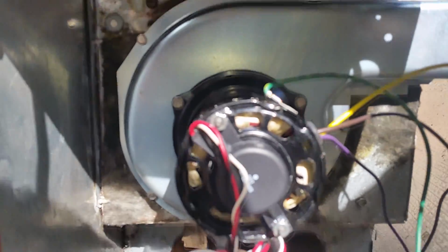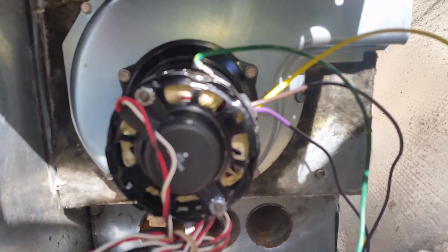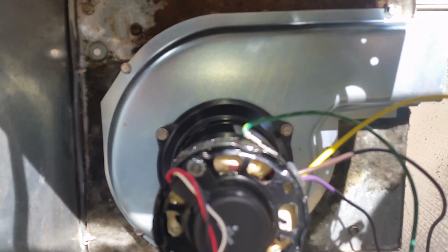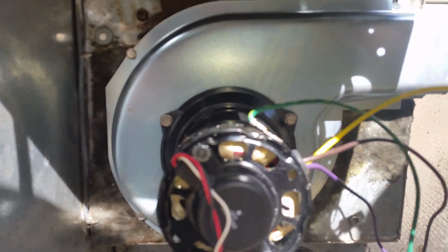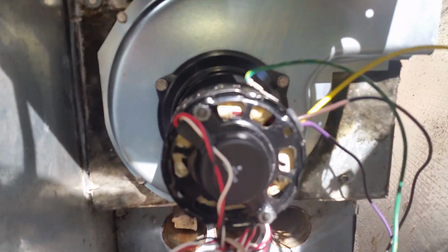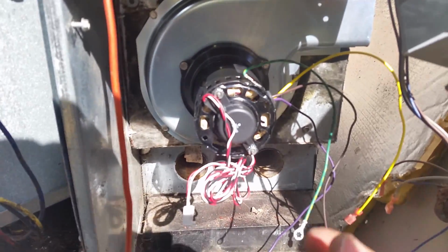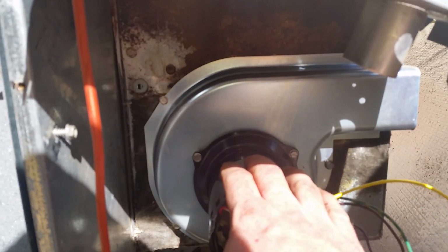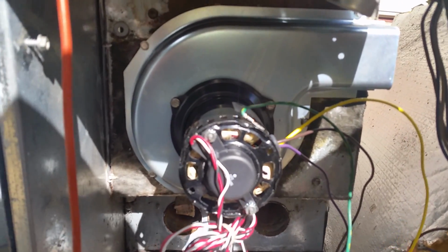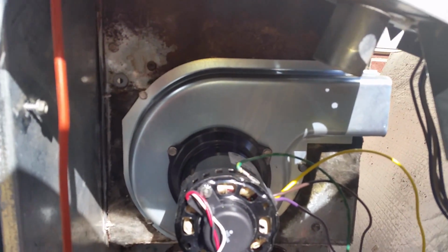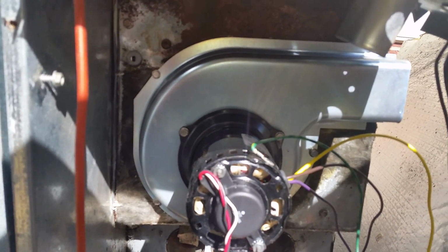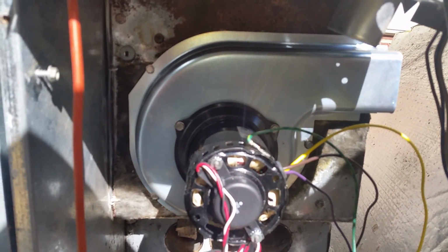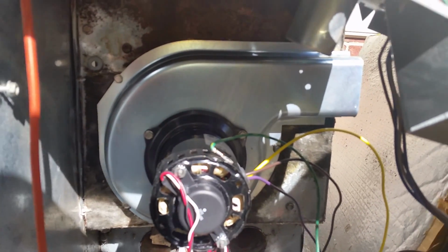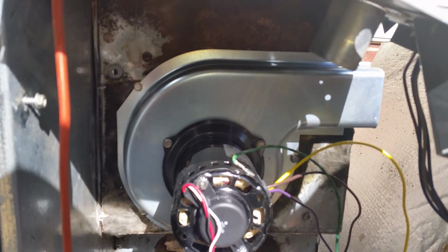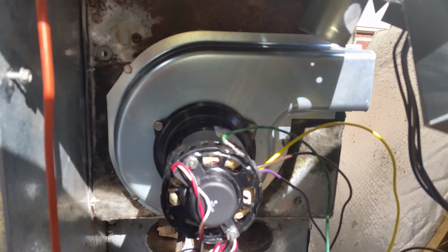Okay, we got the draft inducer in place. Now these screws here, you're going to tighten them up, but you're probably going to have to make some adjustments because that fire plate, depending upon how old it is, may have warped a little bit. And so you'll get a brand new draft inducer making noise, a scraping noise. It's where the squirrel cage is not warped, and so therefore it's hitting up against some part of the firewall plate that is warped.